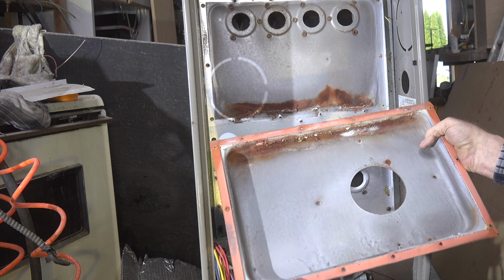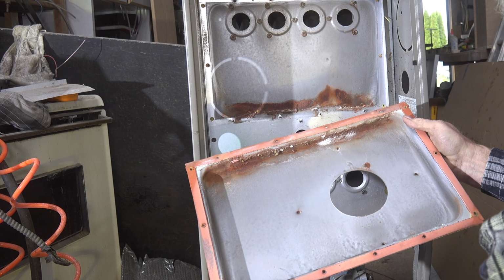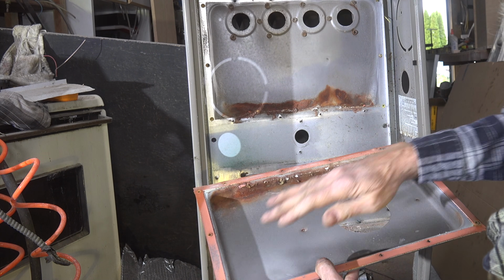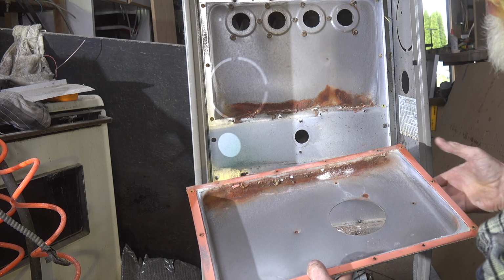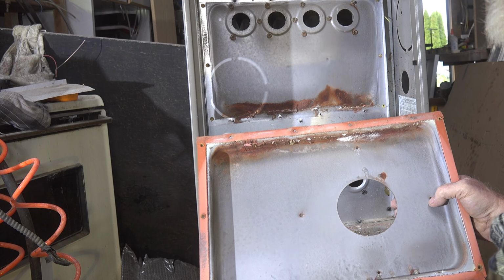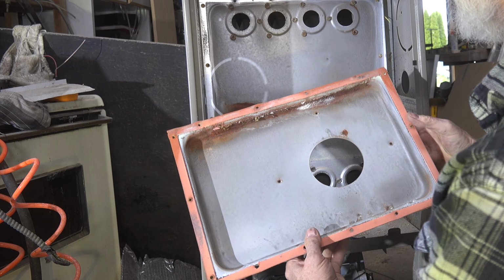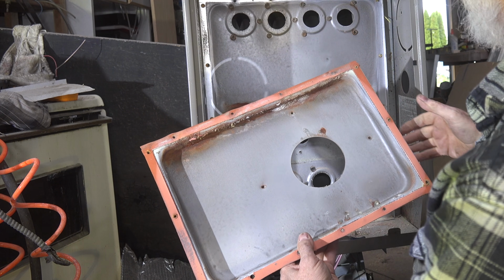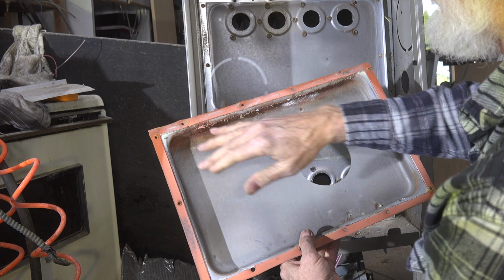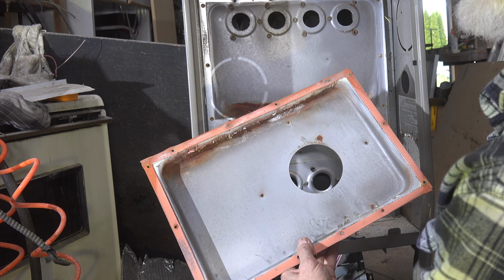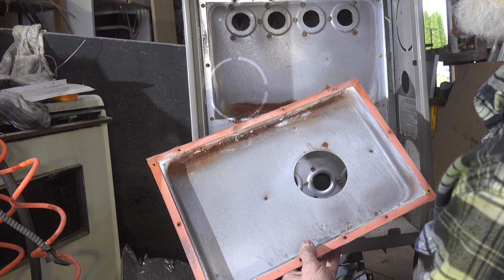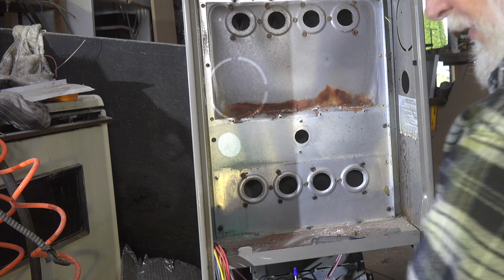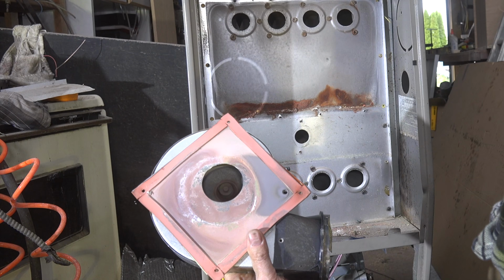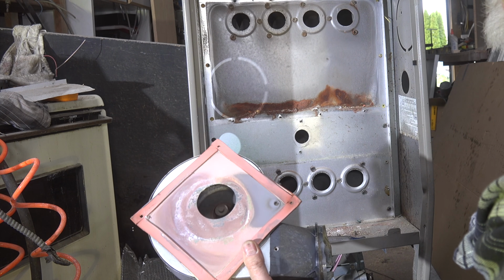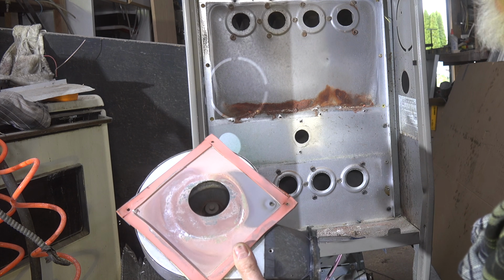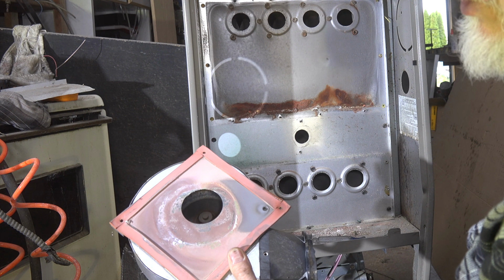Okay, now what you've got here is a manifold assembly that if they did not provide that, then you're going to have to reseal this. Now if they gave you this strip of insulation, you just take that off and scrape it and put it on. If you didn't get it, you still need to take this stuff off and use some high temperature silicone in there. That'll work fine. Same thing here on the inducer. If you get the strips, put them in. If not, you're going to have to use silicone on them.